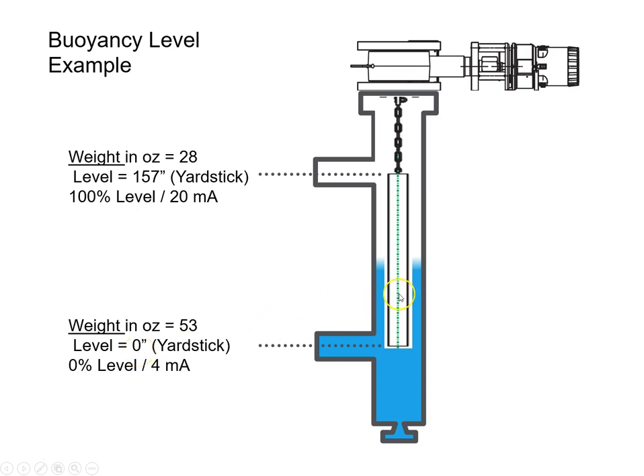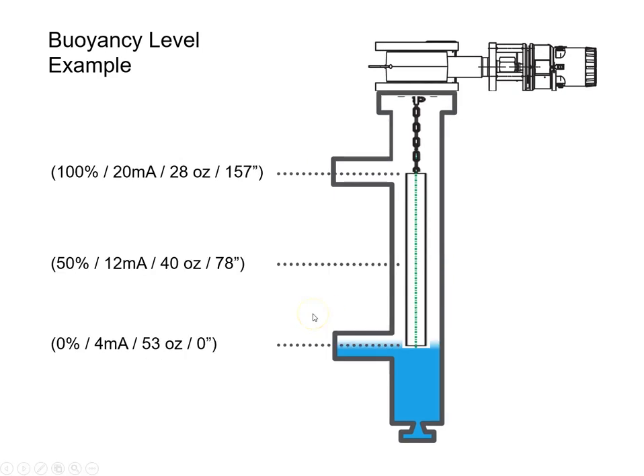By the way, the displacer isn't afloat — I've heard it called that before. The displacer remains stationary and it doesn't float. If you're thinking it's strange that the lower level has a heavier weight, you're not alone. It looks a little odd that we have 53 ounces at the lower level, but I'll explain it. It's heavy because when you look at the displacer, it's hanging in air — there actually is no level; we're at 0% or 0 inches. The liquid is just below the displacer, so since there's no buoyant force to make the displacer feel lighter, it's hanging in air and it appears to the instrument to be at its heaviest: 53 ounces.